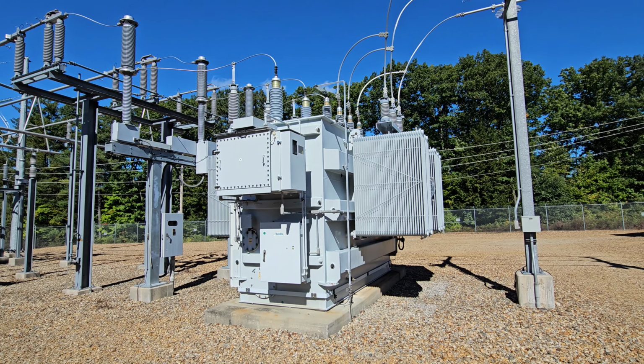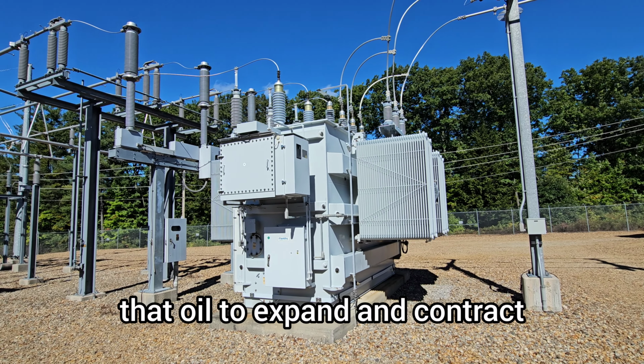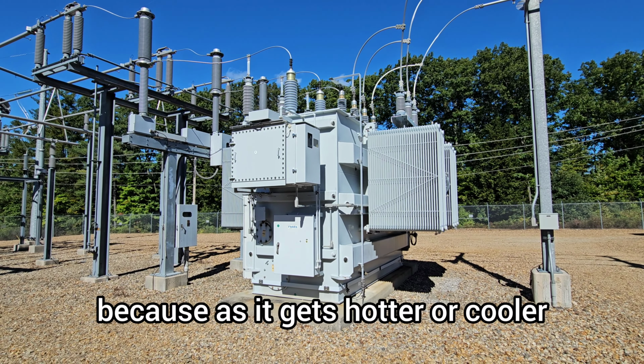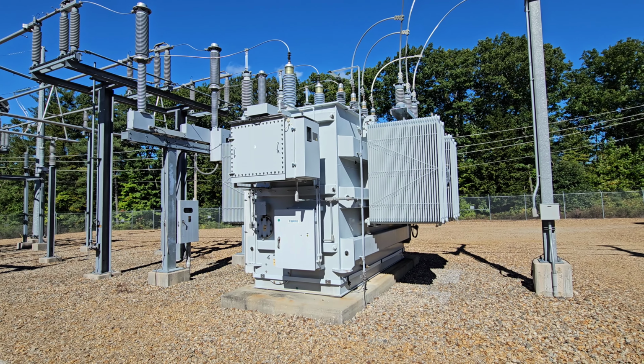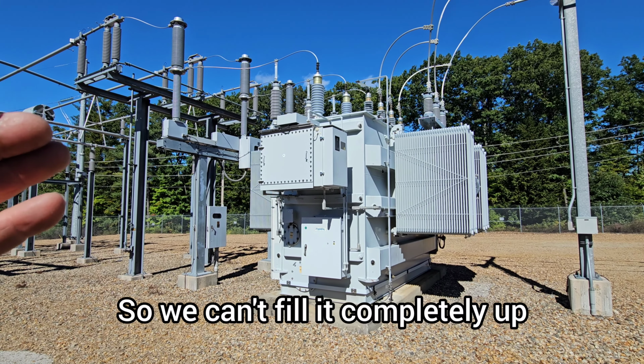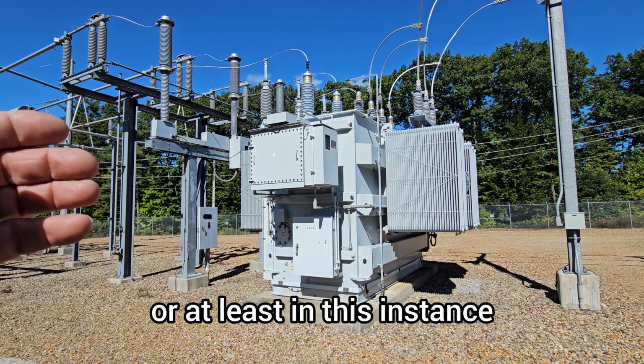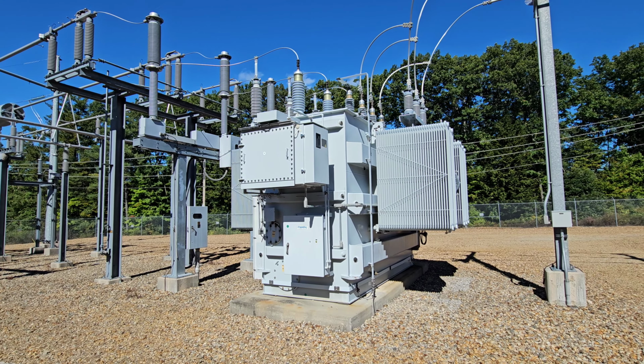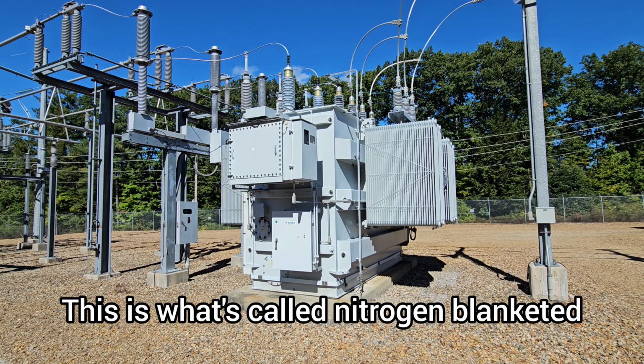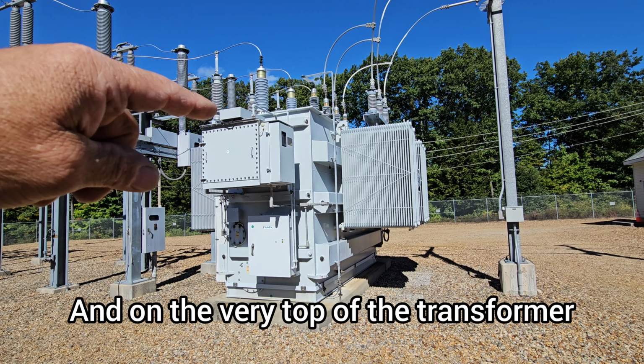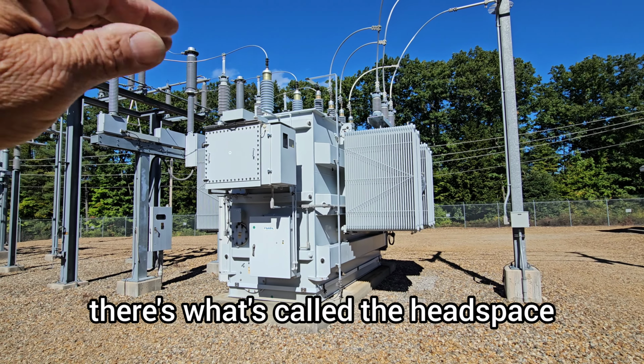The thing is, you have to allow for that oil to expand and contract, because as it gets hotter or cooler, it expands and contracts. So we can't fill it completely up, or at least in this instance, this type of transformer is what's called nitrogen blanketed. On the very top of the transformer, there's what's called the headspace.